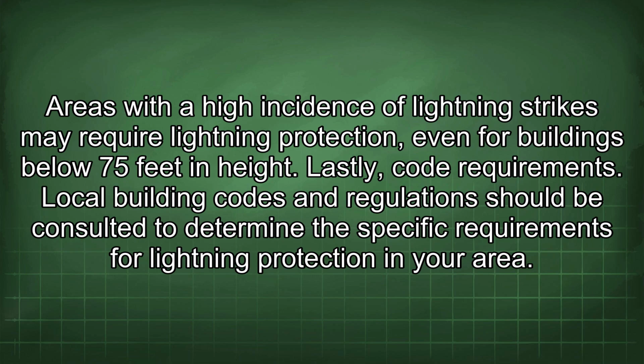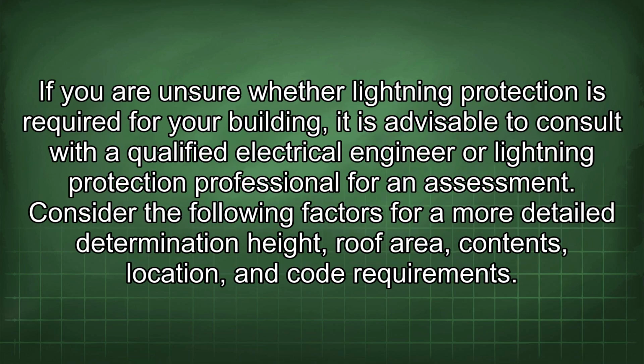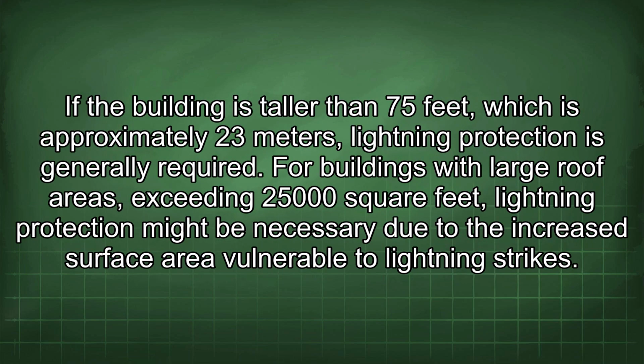Local building codes and regulations should be consulted to determine the specific requirements for lightning protection in your area. If you are unsure whether lightning protection is required for your building, it is advisable to consult with a qualified electrical engineer or lightning protection professional for an assessment. Consider the following factors for a more detailed determination: height, roof area, contents, location, and code requirements. If the building is taller than 75 feet, which is approximately 23 meters, lightning protection is generally required.